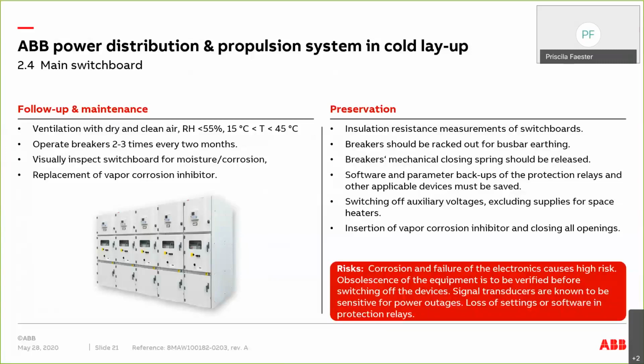For the preservation, it's good to make insulation resistance measurements again to see the insulation condition of the equipment. And then breakers should be racked out and the bus bar earthed when there's no power anymore in the switchboard. And closing springs on the breakers should be released so that they don't remain in tension for years of time. Of course, if the breakers have been operated 2 to 3 times every 2 months, then it's not that big a problem if the spring is not released. But when it's left for a longer period of time, it's a must that they are released.